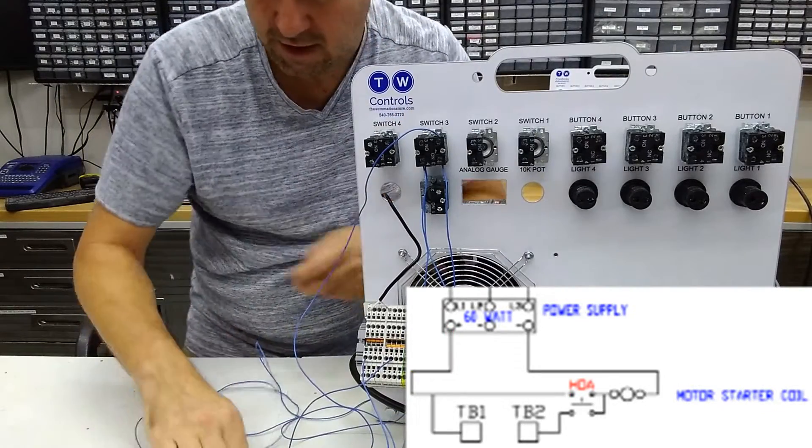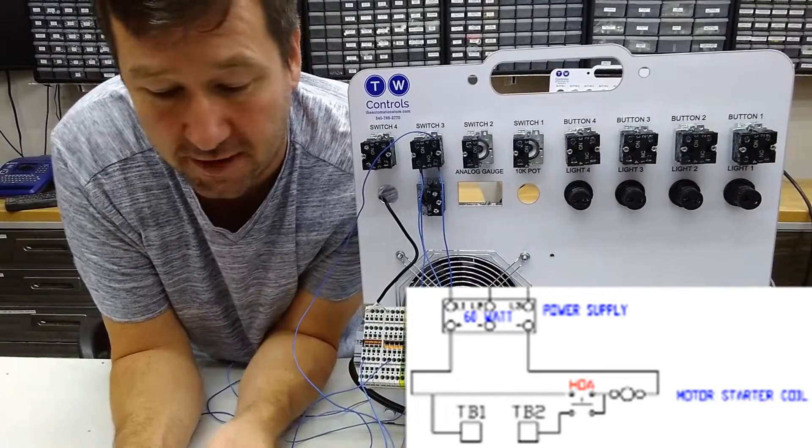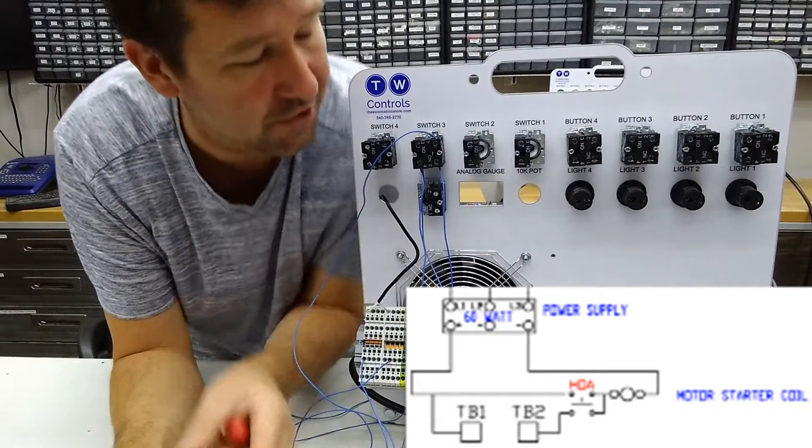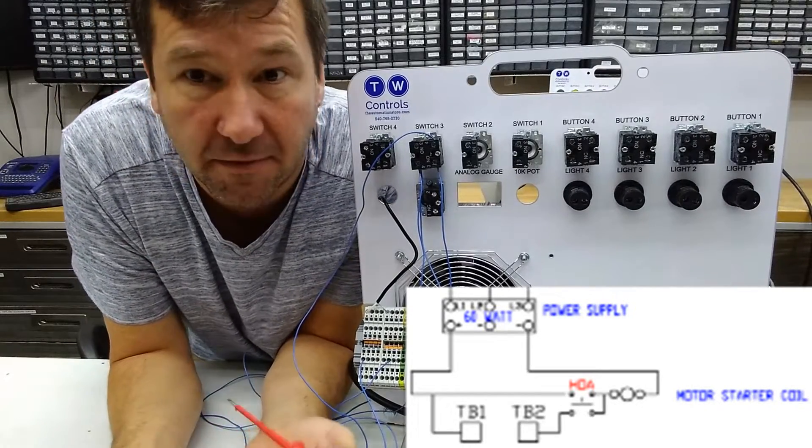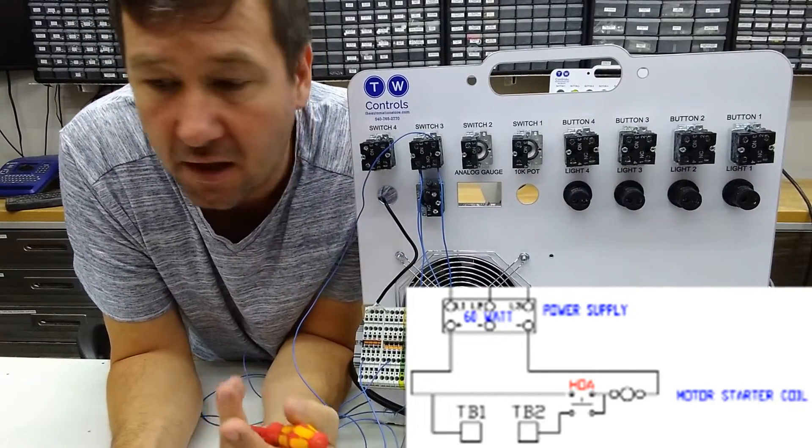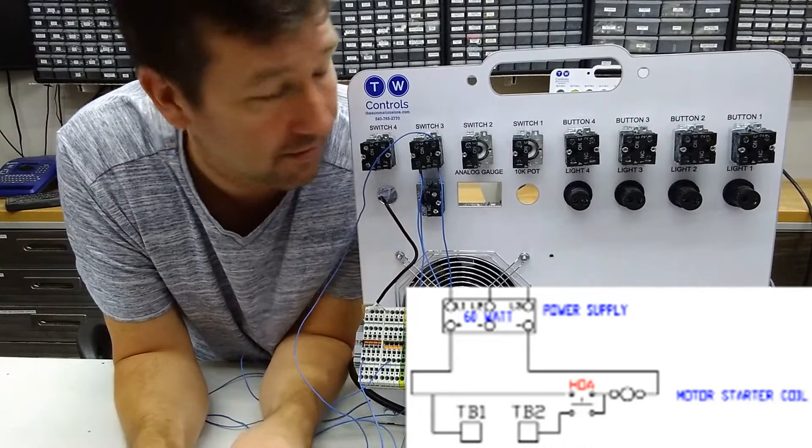But now for the auto. And you notice in the auto, there's just kind of two wires going out to a set of terminals. And this is typically what you would see. So these two terminals would continue on to say maybe a float switch in a pump station, or something that will automatically operate this system.